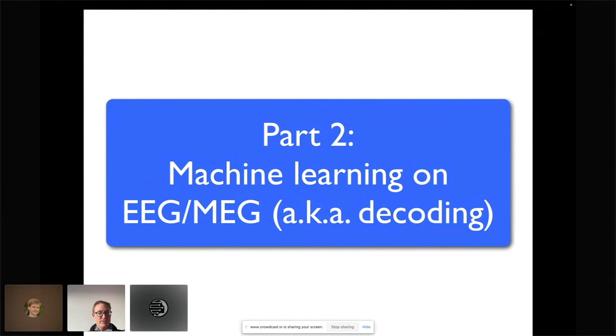So Alex, we had two questions on artifacts. One was about the slow drifts and what they mean. Typically your SQUIDs are sensitive to environmental perturbations. If you have anything that is slowly moving, or any electrically charged structure that is moving in the vicinity, it will produce these very slow global field changes that you will see in all of your magnetometers at the same time.